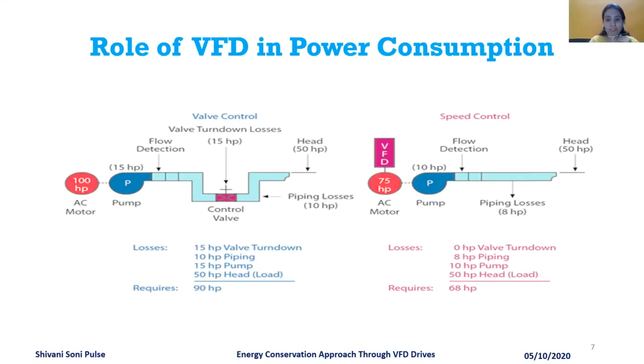a 90 HP motor. Now instead of that, if we employ the VFD in the system and control the motor with the VFD, we can simply eliminate that control valve, so the losses of the control valve and the mechanical losses are reduced in the system, and we see that around 70 horsepower is required to run the motor at the full speed of the pump. So we can say that nearly 20 to 30% of power consumption is reduced while using the VFD. This calculation is based on the energy consumption of the affinity laws.